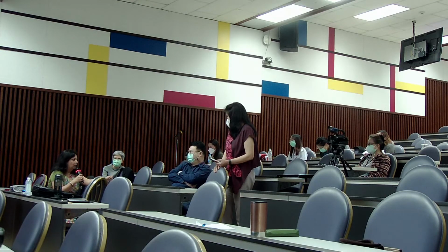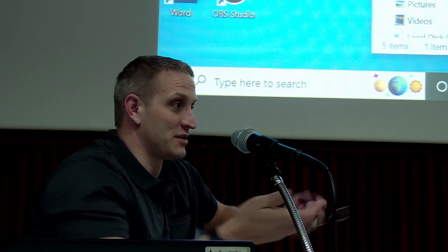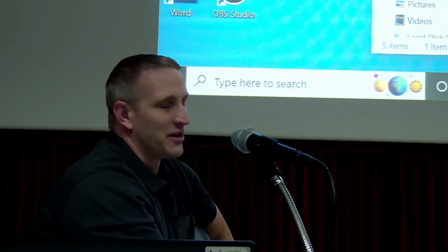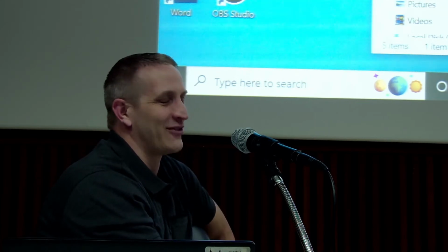They put the law down, but then I think there's a problem. It depends if the parent is reading the report and they freak out. Oh my God, this number is so much higher, right? Well, that was the problem, because the state came out and said, thou shalt put the patient dose in the report. But CTDI vol and DLP are not patient values. And so immediately the radiologists said, well, what do we include? And that's actually where SSDE was developed. It was a need to create some kind of patient-specific dose, even though technically SSDE is still not patient dose. So you have to be careful. Regulation will drive changes that aren't meaningful. So you have to be very careful with that.